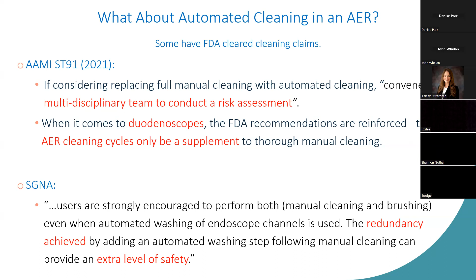And when it comes to duodenoscopes, the FDA recommendations are reinforced that AER cleaning cycles are only a supplement to thorough manual cleaning. SGNA states the same, and they emphasize the value in that purposeful redundancy of having manual cleaning followed by automated cleaning. The other thing that it's not uncommon that an infection preventionist may or may not be aware of is whether the cleaning cycle is turned on in the AER. Automated endoscope processors have an automated cleaning cycle and an automated HLD cycle. It's worth validating whether you're relying fully on manual cleaning at the sink, or if you're including automated cleaning in the machine.